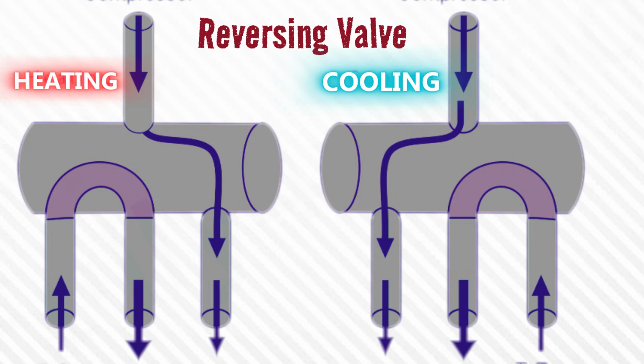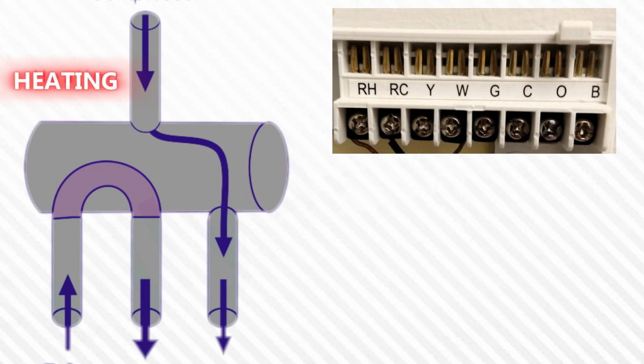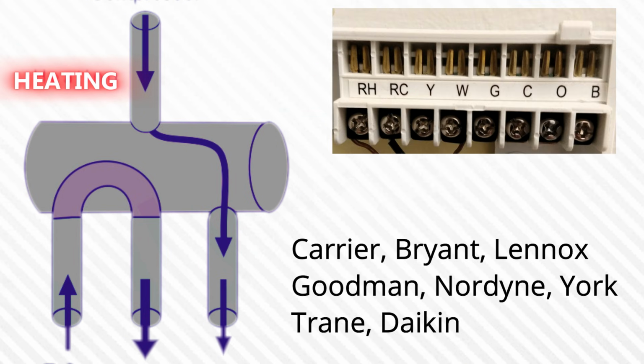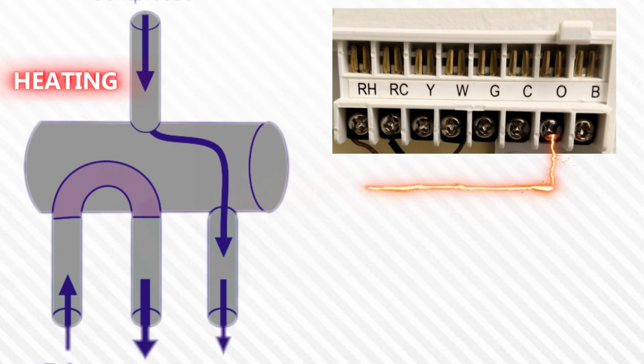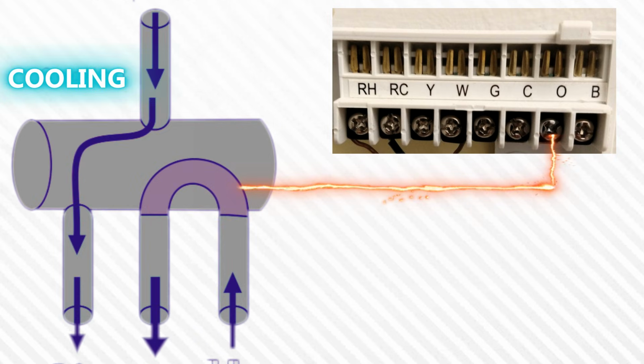All reversing valves have a default position when they're not energized. Some of them default in the heating position, some default in the cooling position. Now, a lot of the major brands out there, their reversing valves default in a heating position, which means we have to energize that valve in order to get cooling mode activated. And that's exactly what the O terminal does. It gets energized when the thermostat calls for cooling and it sends 24 volts on that O terminal.